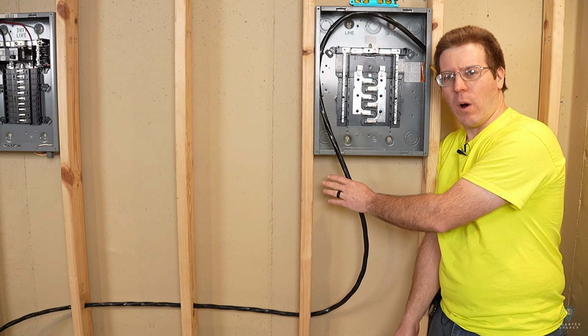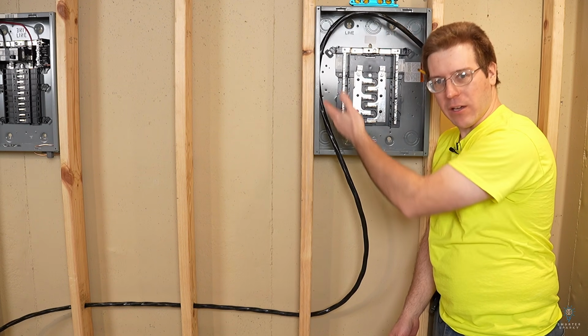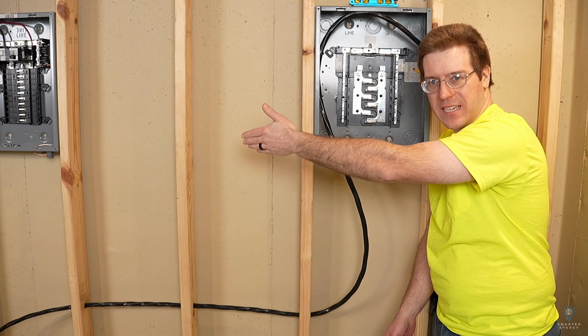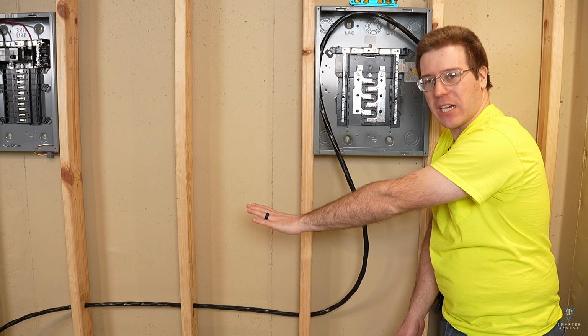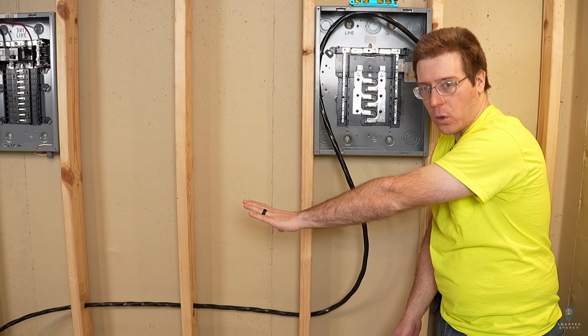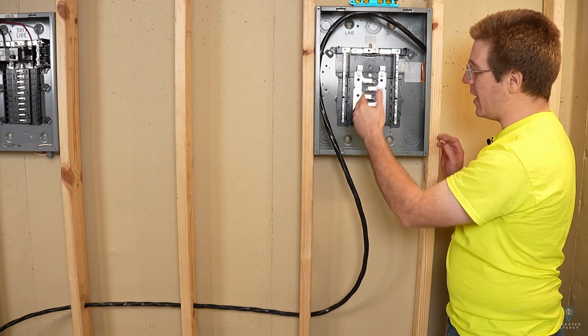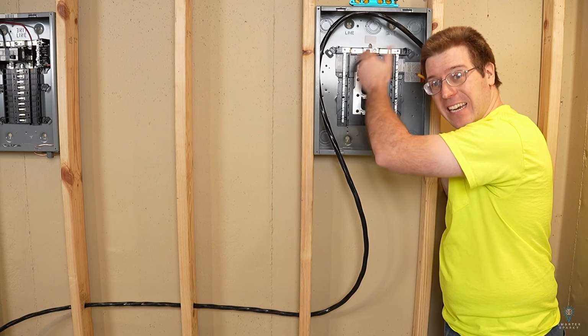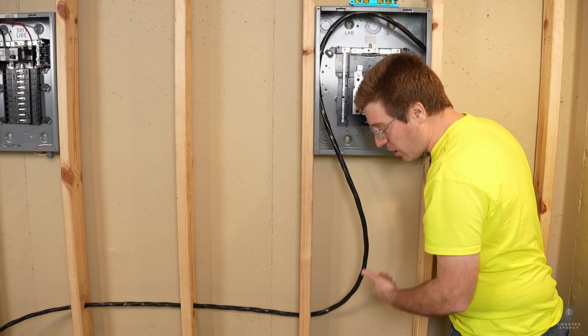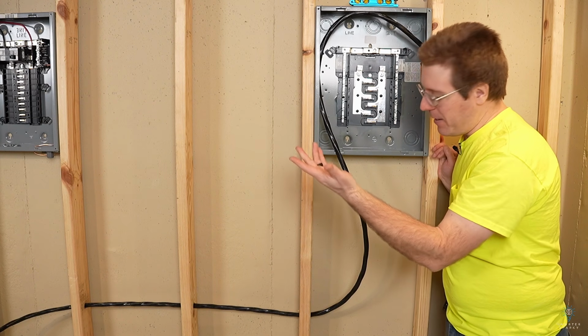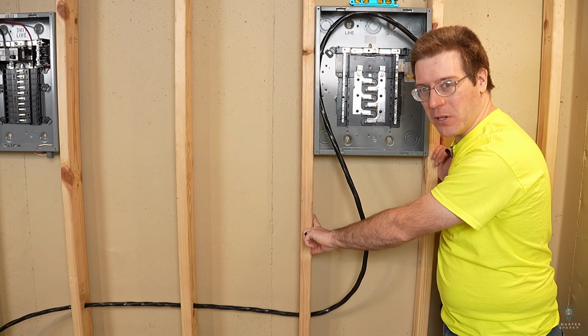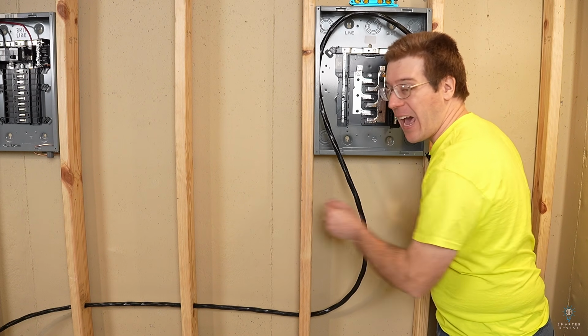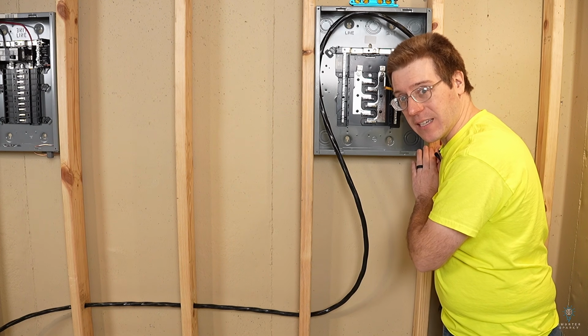With this thicker wire, I like to actually start working it right away from the back towards the destination. So I'm not even gonna cut anything off of that end of the spool right now. What I'm actually gonna do is we're gonna strip this out and get it into this panel first, and then start stapling it all the way back. In this case, we're really only gonna need one staple down here. The studs actually act as the support horizontally in this case.